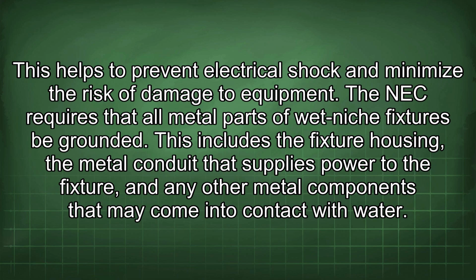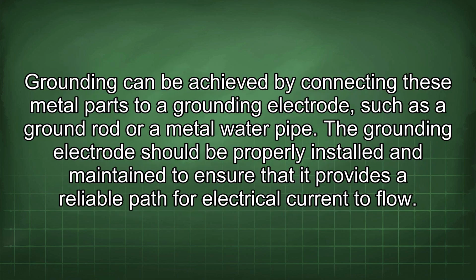This includes the fixture housing, the metal conduit that supplies power to the fixture, and any other metal components that may come into contact with water. Grounding can be achieved by connecting these metal parts to a grounding electrode, such as a ground rod or a metal water pipe. The grounding electrode should be properly installed and maintained to ensure that it provides a reliable path for electrical current to flow.